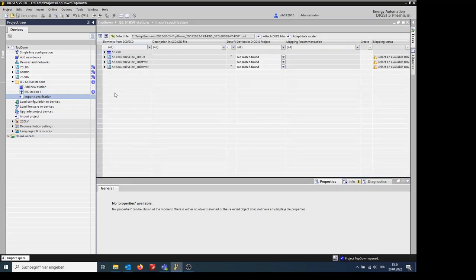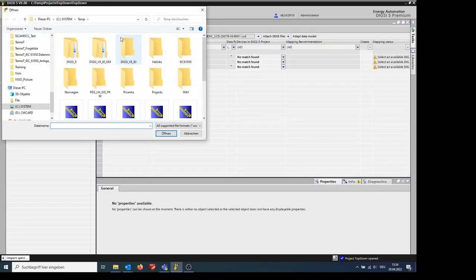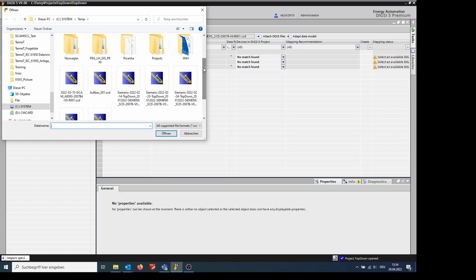Now I will show you the steps for importing the IEC 61850 system specification in DIGSI 5. On the left side, click on IEC 61850 stations and then select Import Specification. Now click on Select File. You can then select the SSD or SCD file to be imported.